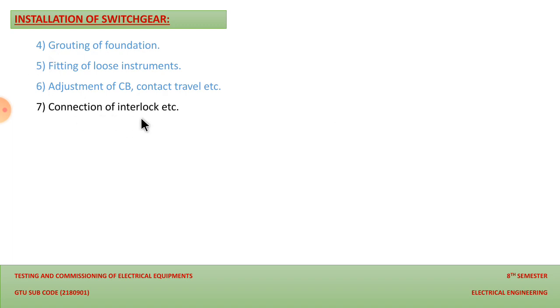And the connection of the interlock, etc. This is an important point, because a person who is unfamiliar with the switchgear will not touch or operate the switchgear. That's why the connection of the interlock is necessary. And the eighth point for the installation of the switchgear is filling up of the oil in the oil circuit breaker. It is obvious that for the oil circuit breaker we generally use oil as insulation. So before we take our switchgear into operation, we should fill it with the oil.